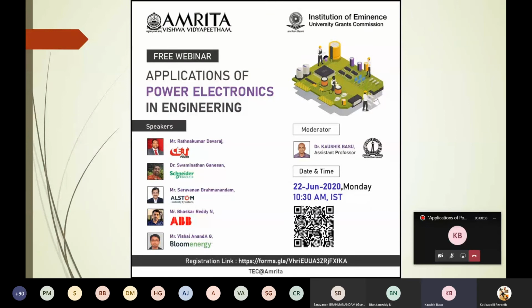So the thing is, what I understand is that from the DC link of the rectifier of the UPS, typically there is a DC to AC inverter which is powering the AC load through the static transfer switch, where your grid is also directly connected. So in case of a grid failure, the DC to AC inverter of the UPS will take over through the STS, correct? And you talked about the reliability issue with STS, that it may malfunction.